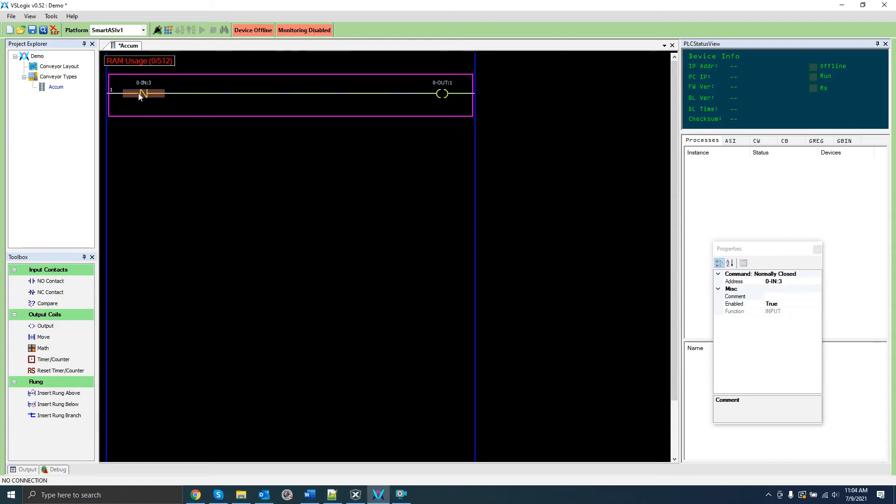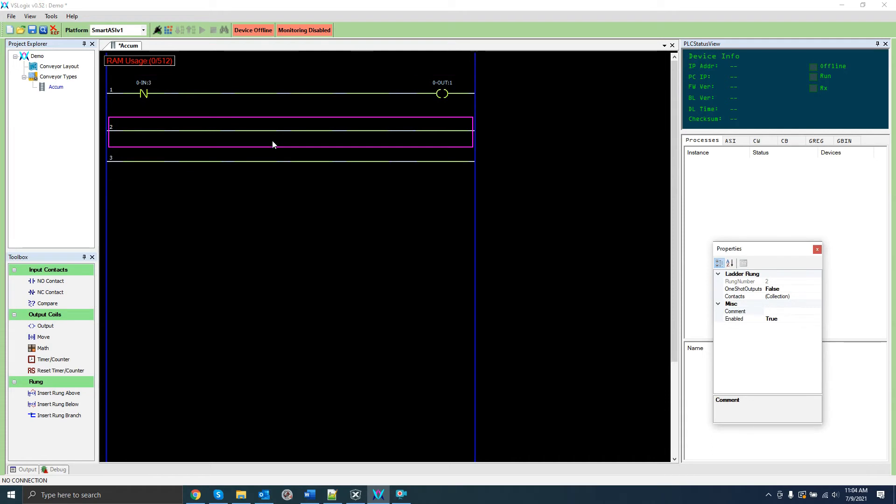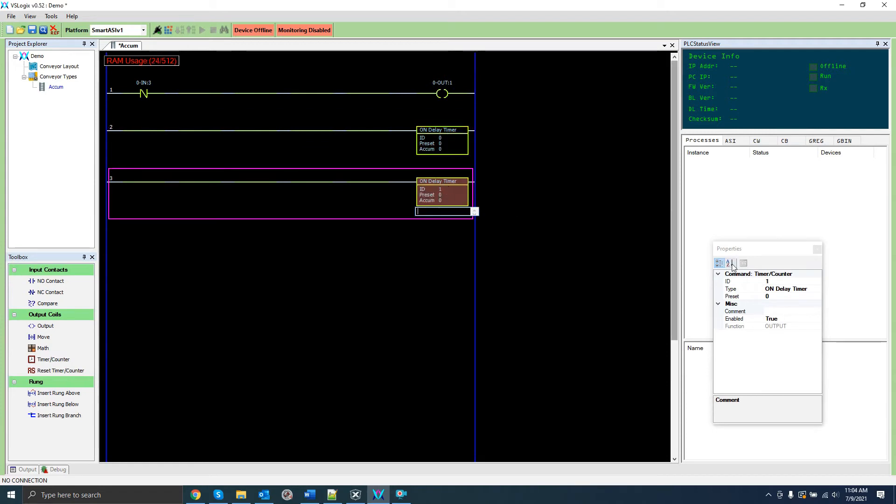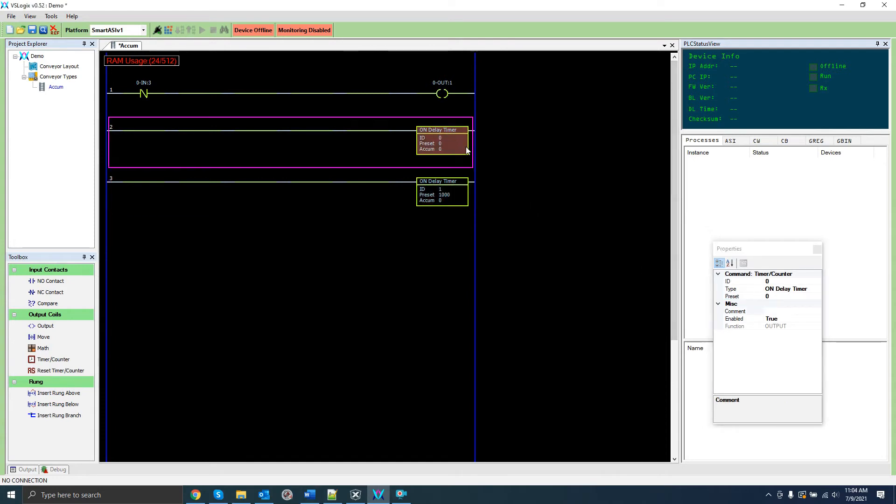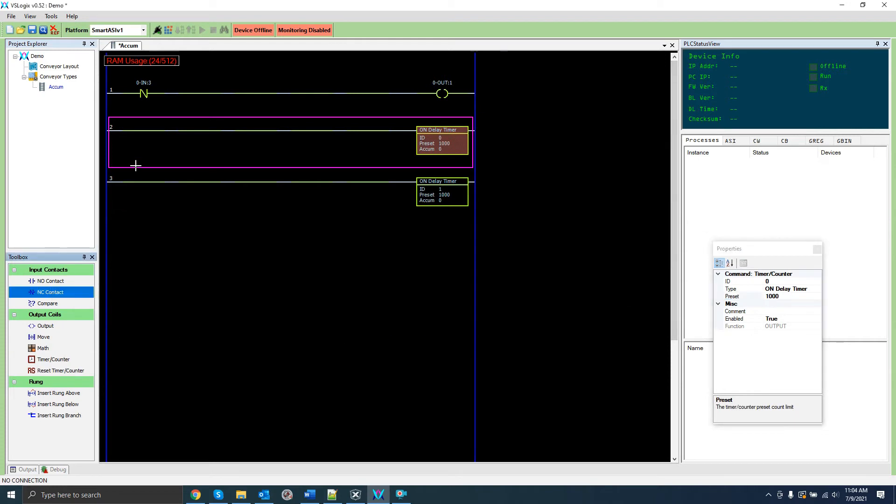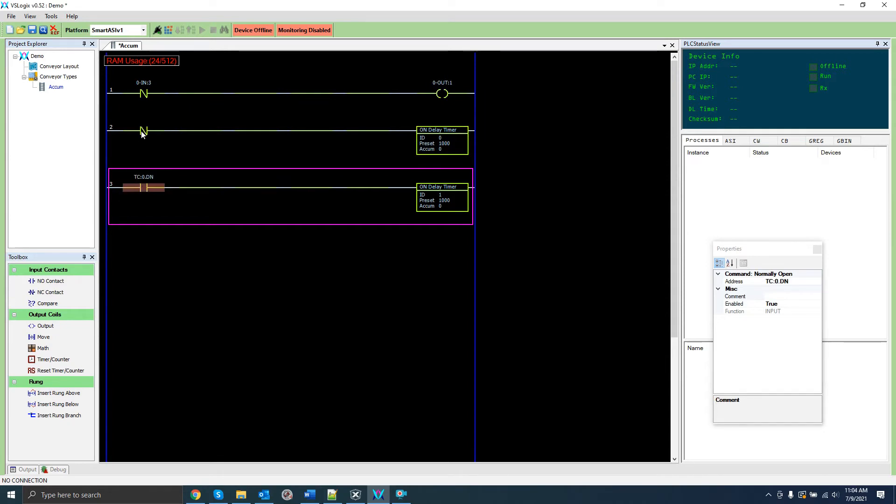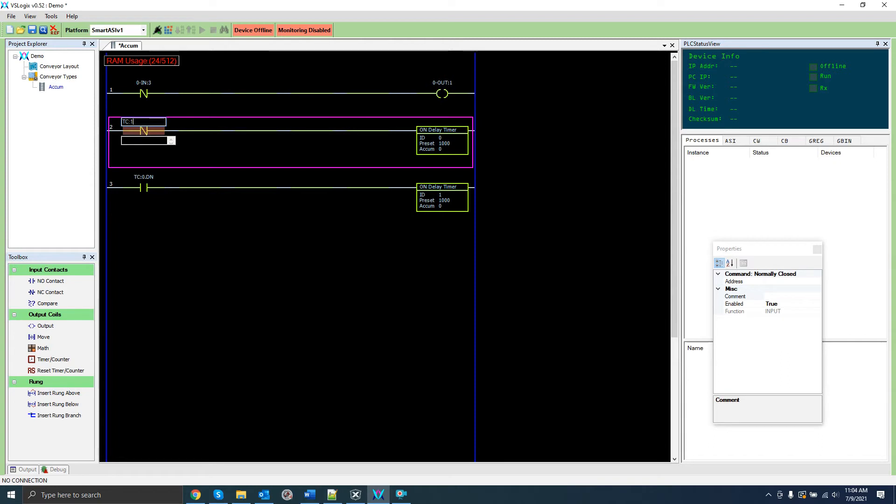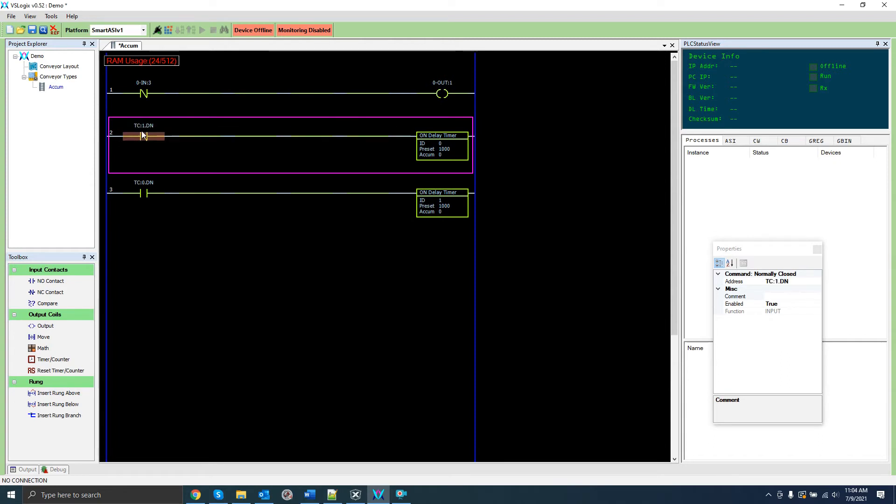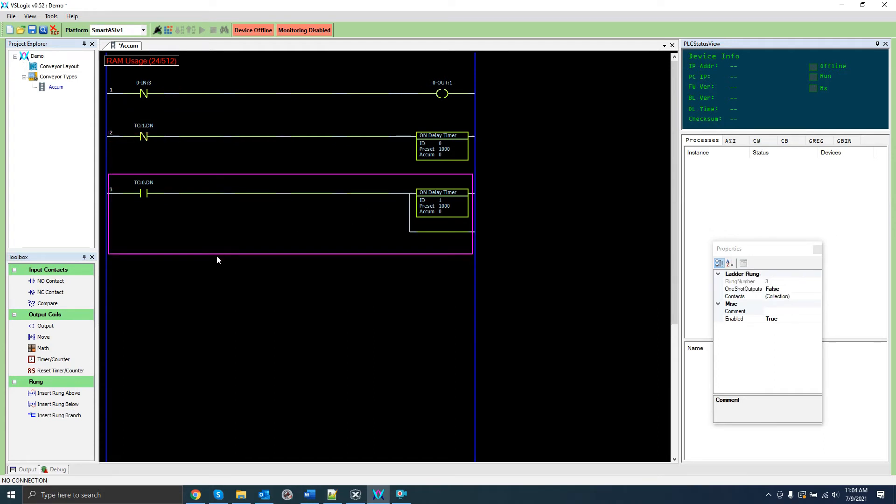I'm going to set up another output but make this one blink. There are two ways to accomplish this. For the first I'm going to couple two timers together. I'll first add two rungs then put a timer counter coil on each. By default these are configured as timers, which is what we want. I'm going to set the preset for each to 1000 milliseconds. On the first rung I'm going to put an NC contact and on the second I'm going to put an NO contact. And set the address of each like so. The TC file type stands for timer counter. As the name suggests, each index of this file type corresponds to a timer counter coil in the Ladder program. The .dn suffix means that the contact will be active when the timer has reached the defined preset. By setting the two timers up like this they will alternate between each other. Now we just need to put an output coil on a branch off the second rung and our output will blink.